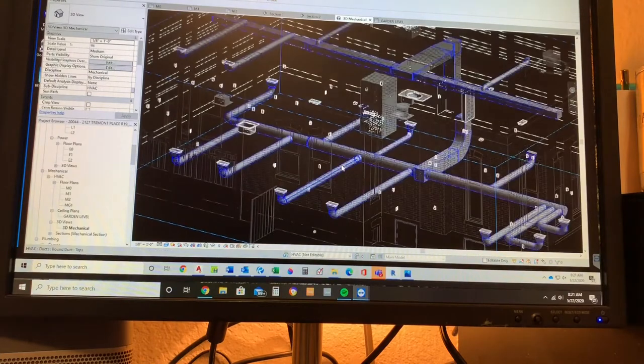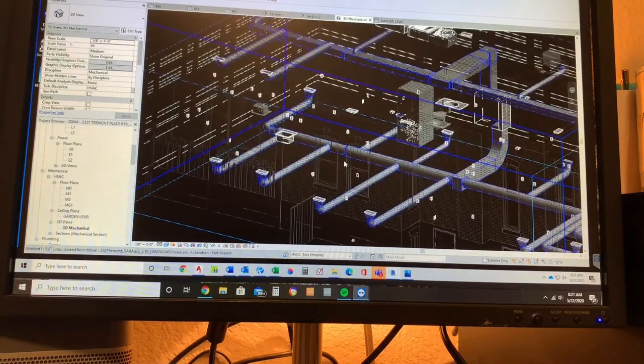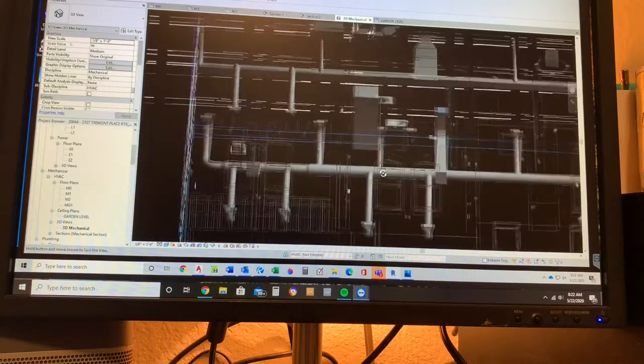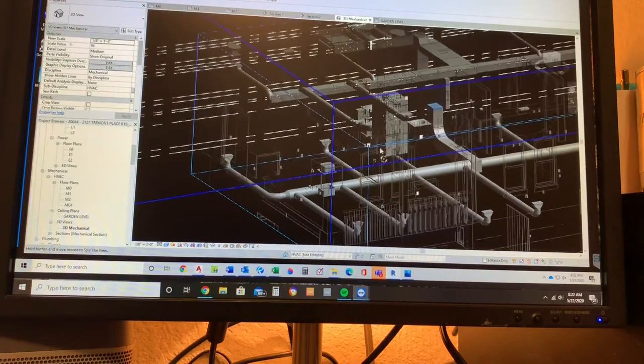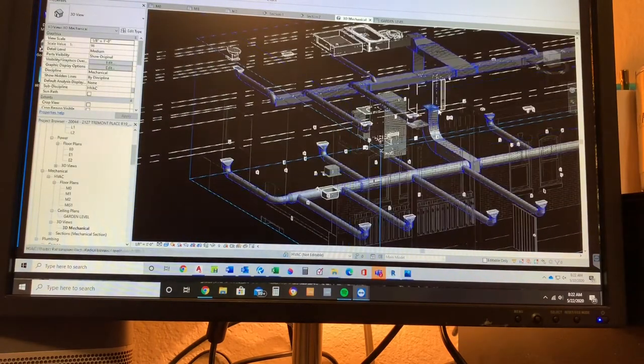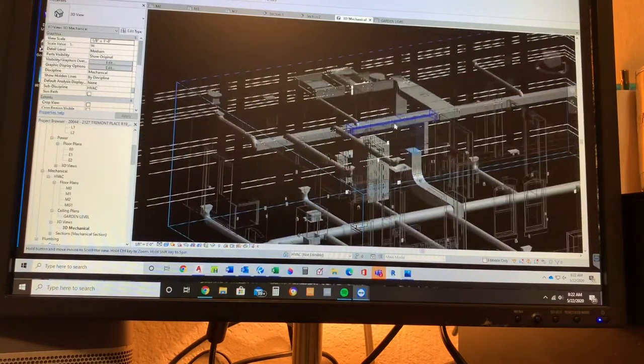That's per fire code. This project is under the 2018 International Building Code, which falls under the jurisdiction of the 2018 series of the International Fire Code, Mechanical Code, and Energy Code — which are getting more strict every year. Energy performance and efficiency is pretty important. We're going to achieve our ventilation through the house by using two-speed exhaust fans, which I've yet to model. They're going to be in the ceilings of each restroom — what happens is the fan always runs at a low speed, therefore pulling fresh air into the space through cracks in the building, known as infiltration. The air comes through window gaps and door gaps primarily, or through a leaky building envelope.